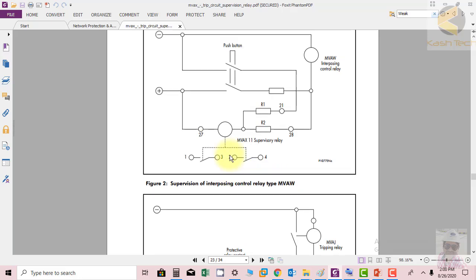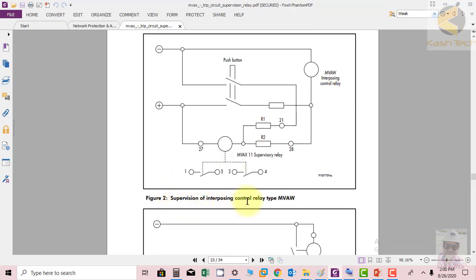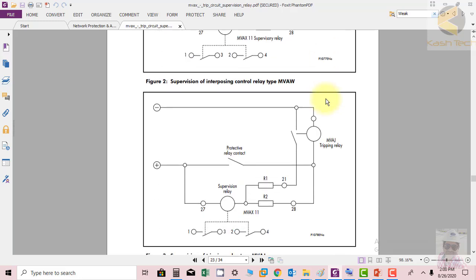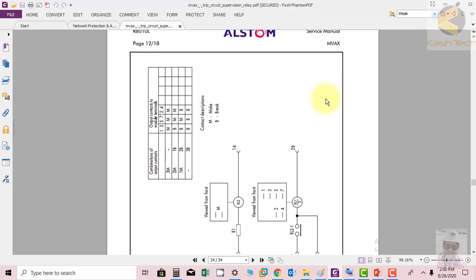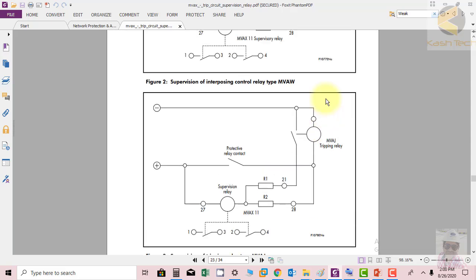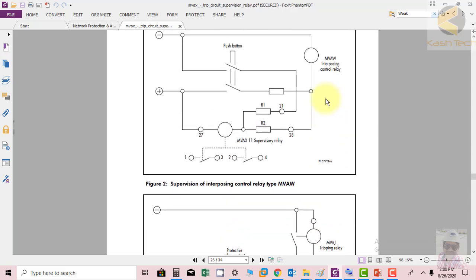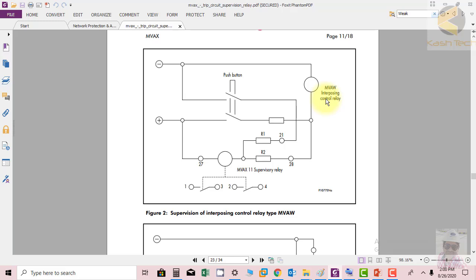And here you can see the MVAX is supervising the interposing relay, MVAW. This is some kind of control relay. Another scheme that I have seen in Aramco is that the tripping circuit is supervised by a relay, and that relay is again supervised by another relay. So they have double checked the system.